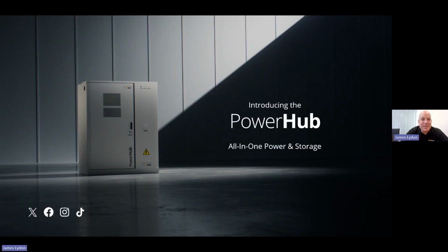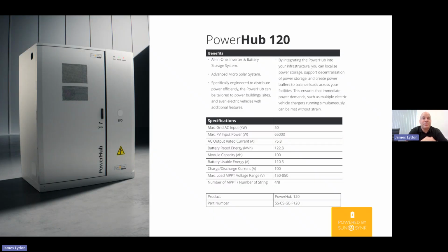Okay, so we're getting a little bit bigger scale now. I'm not going to cover the big 2-3 megawatt hour containers that we do. But the Power Hub is really popular in agricultural settings. So the PowerHub 120, inside it is essentially a 50 kilowatt hybrid inverter and 2 61.4 kilowatt hour stacks in a self-contained unit. So there's full HVAC, cooling, heating. You've got gas detection and fire suppression built in as standard.